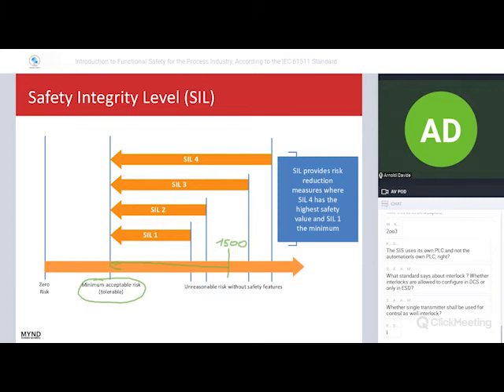But anyway, we have to follow the life cycle of the standard in order to reduce this risk. In the case of, for example, 1,500, we establish the SIL level, that is SIL 3, and then there are many requirements inside the standard for redundancy, for architecture, for capability, for a lot of things. So the output of our SIL allocation is, first of all, to define the SIL level as the risk reduction needed to move to the tolerable zone. Then, with this information, I have to design the safety instrumented function in order to move from 1,500 to 0, for example. But we cannot speak about risk 0.